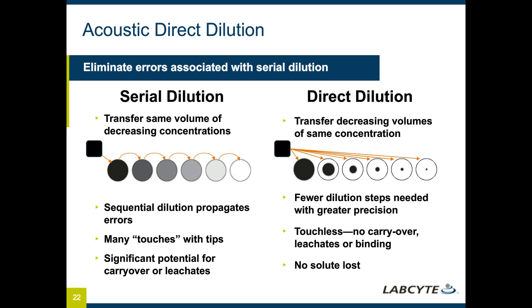Now, when you have an instrument that is capable of transferring such small volumes as the Echo, you can start to think about doing things like what we call direct dilution. So using the same example, we're starting with that high concentration sample contained within the box, and we're taking smaller and smaller aliquots of that and directly diluting into there. So each of those may have a certain error associated with it, but those errors are not propagated across the dilution series as you make them. And so that's incredibly powerful in terms of increasing the precision of any dose response curves that you may be creating. So the way this would be applied is depicted in this slide here.